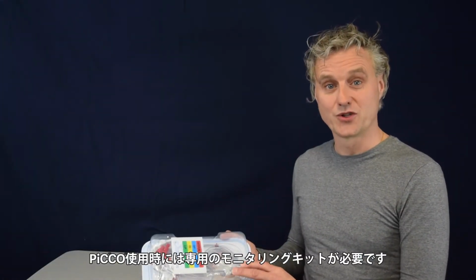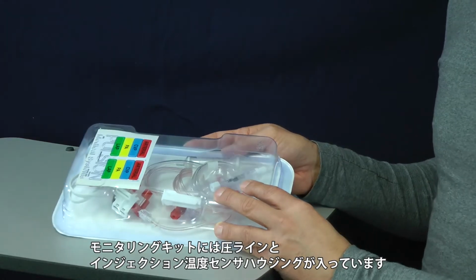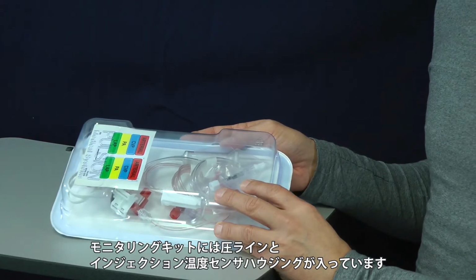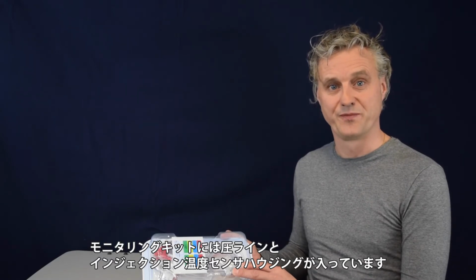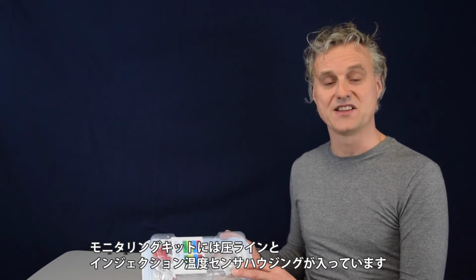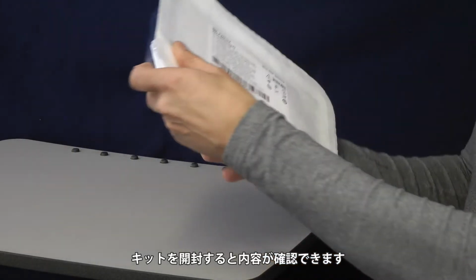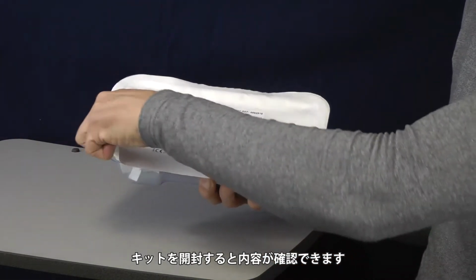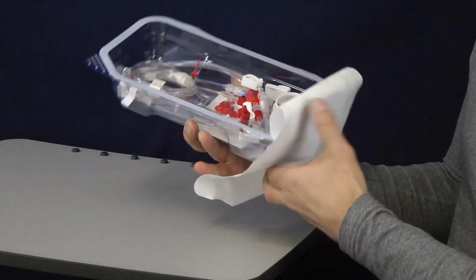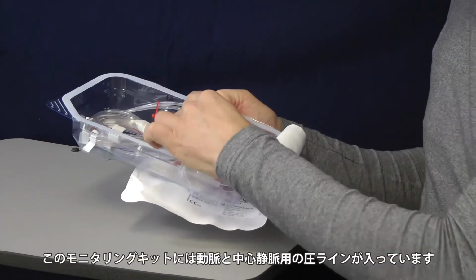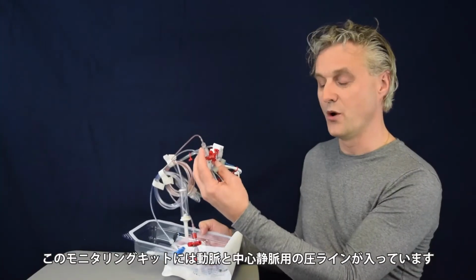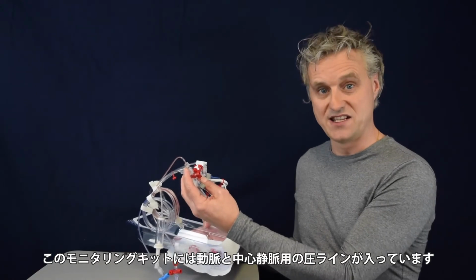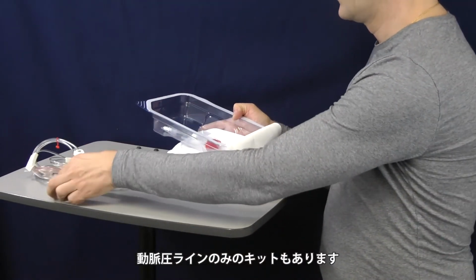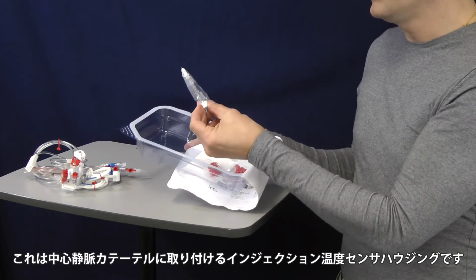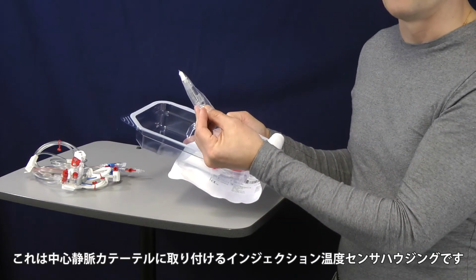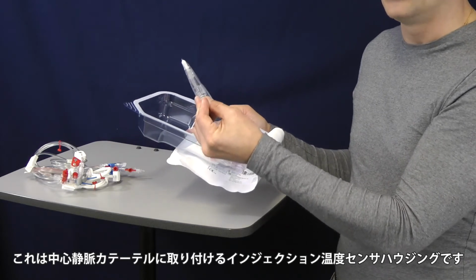Besides the PiCCO catheter, you also need a monitoring kit. This monitoring kit provides you with an arterial pressure transducer and a central venous pressure transducer. Included in this kit, there's an injectate sensor housing. When opening the box, you will find the right items inside. Here you can find the two pressure transducers, which can be connected to the PiCCO catheter and the central venous line. Separately sealed is the injectate sensor housing. You will need this for the connection to the central venous pressure line.